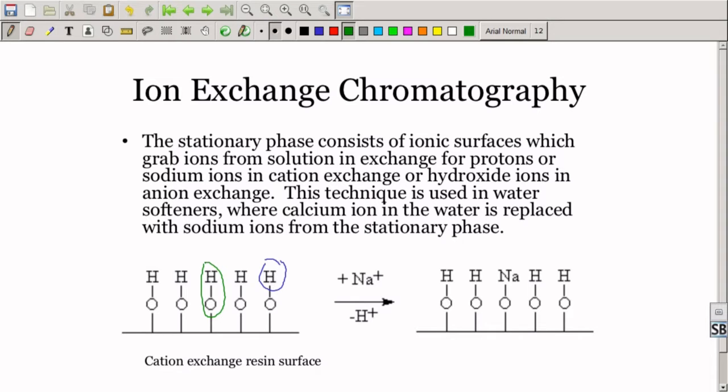And so what you do is you take tap water and you pass it first through an acid ion exchange bed. And what happens is all the cations in that tap water exchange for hydrogen ions from the cation exchange resin. Then you pass the same water over anion exchange resin. Now all the anions that are left will exchange with hydroxide ion. And so the net result is you're going to replace whatever salts you have in there with water.